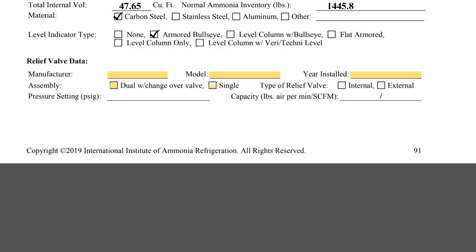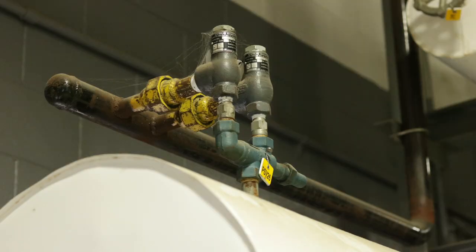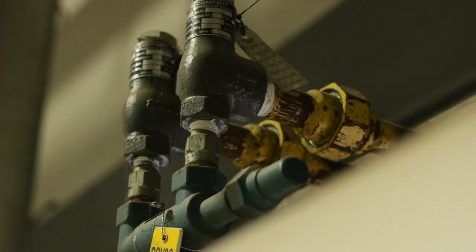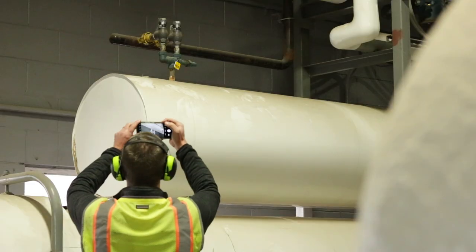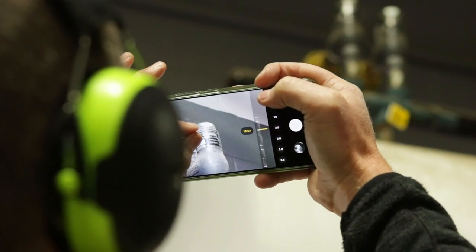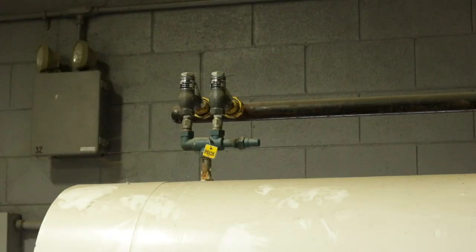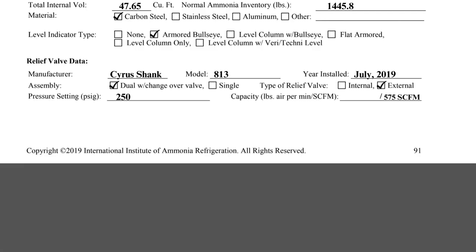The final information required on the first page of the checklist pertains to the heat exchanger's relief valves. The manufacturer, model, pressure setting, and capacity can be obtained from the relief valve's nameplate. If your facility reprints the same completed first page for each checklist, this is one data point on the first page that can change. Be sure to check if the relief valve installed matches what is listed on the form. If the heat exchanger is supplied by a surge drum, then the relief valves will be on the surge drum. For difficult-to-access relief valves, a camera with a high-quality zoom lens can save a lot of time associated with moving ladders around. The relief valves are external to the equipment and terminate to atmosphere, so this configuration is categorized as external.